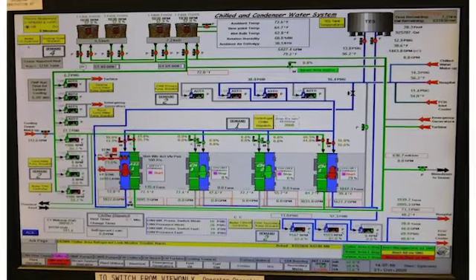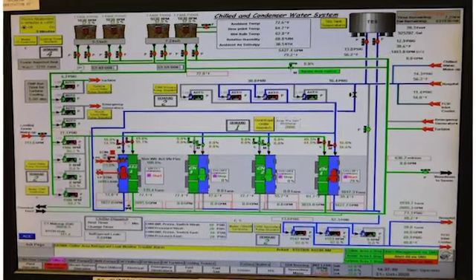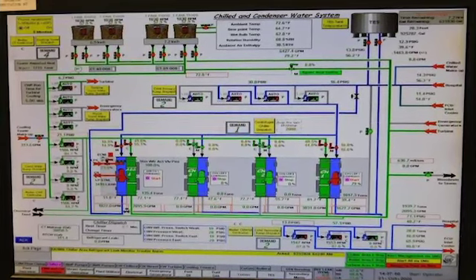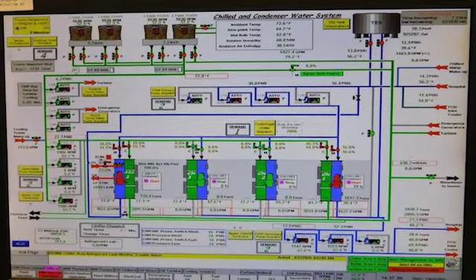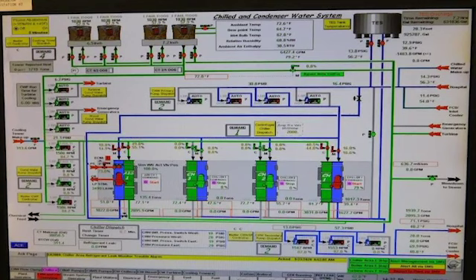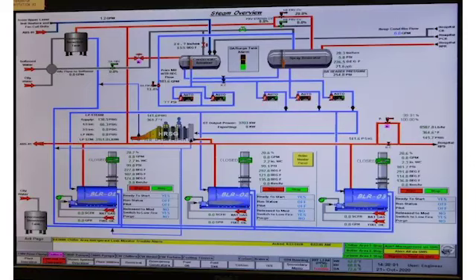And in there, within chilled water, we have Rockwell wire to water optimization, where we're coming up with the right combination of pumps at the most energy efficient dispatch speed, working to either a single or double loop, double PID loop, depending on the pressure and flow. You see the steam HMI here, and again, this is just a quick view. We've seen this before, but again, you've got the three package boilers and the cogen boiler and the HRSG and all the critical parts.